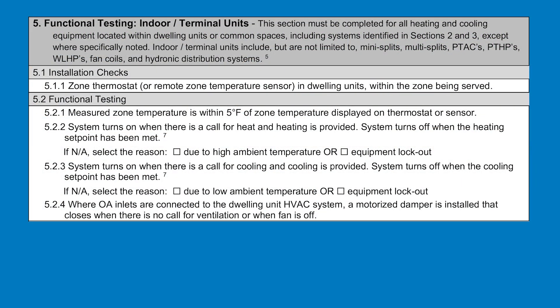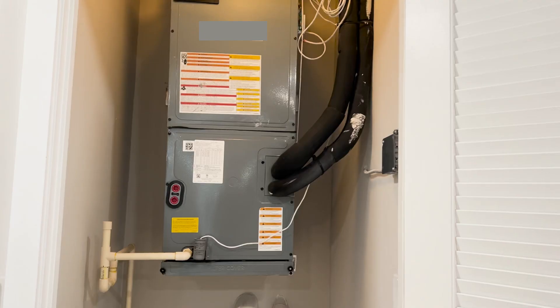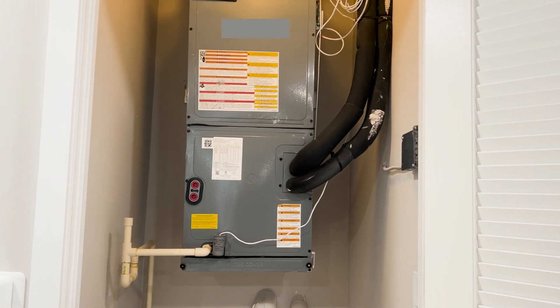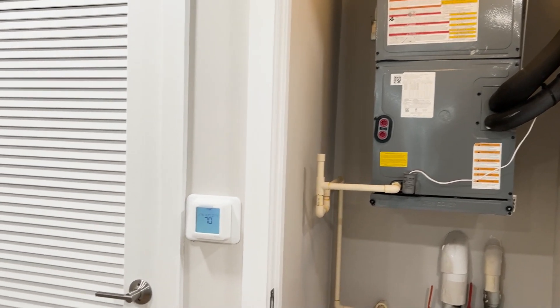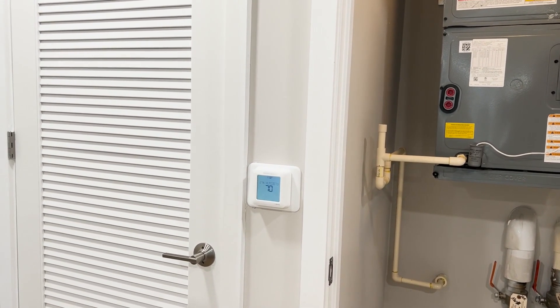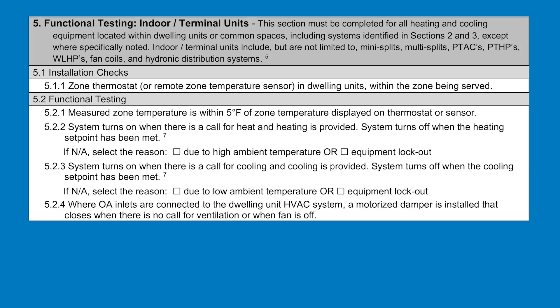Section 5 of the ENERGY STAR Multifamily New Construction Functional Testing Checklist includes two main subsections: 5.1 for installation checks and 5.2 for functional testing. Section 5.1.1 looks for the zone thermostat in the dwelling units. We check that there is a thermostat in the dwelling unit and that the thermostat is in the location that the HVAC unit serves.